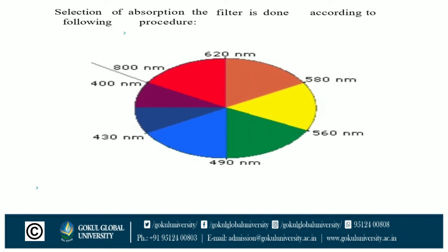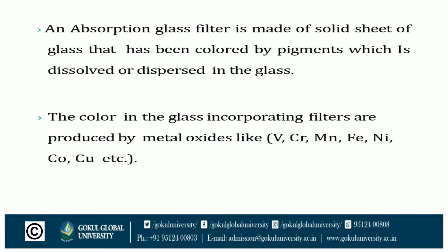A diagram shows the wavelength regions for different colors. If the solution to be analyzed is blue in color, a filter having the complementary color orange is used in the analysis. An absorption glass filter is made of a solid sheet of glass colored by pigments dissolved or dispersed in the glass.